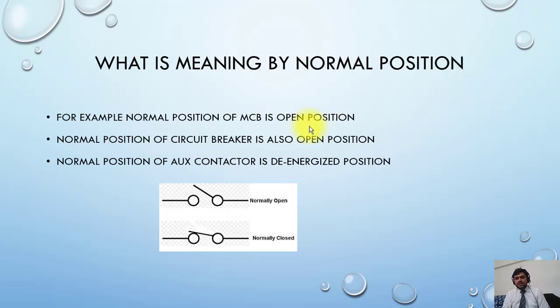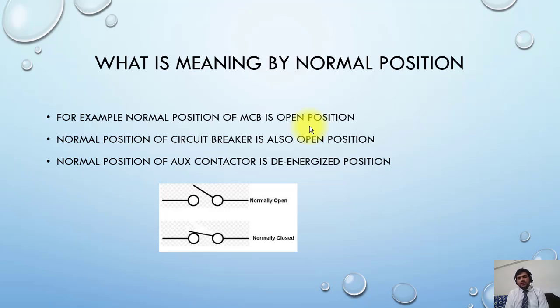In short, the circuit breaker position is considered as open position, and the circuit breaker auxiliary contacts are drawn in open position — the same is shown in the drawing. If you see, the circuit breaker is shown open. This is the normal position of the circuit breaker. All the devices in the drawing are shown in normal position, de-energized position, or open position.